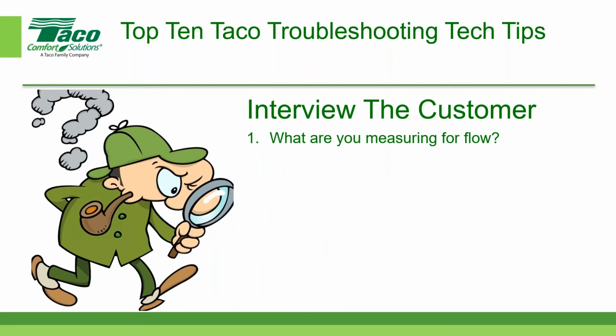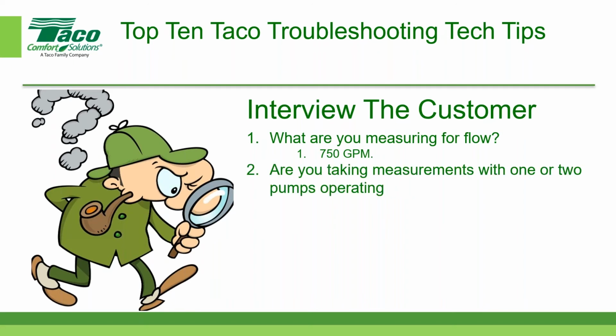So then I said, well, what are you measuring for flow? Well, the design condition we just said was 1,000 gallons per minute, and they come back and tell me they're measuring 750 gallons per minute. Now, we still don't know exactly what the problem is, but we're starting to narrow things down a bit. So I said, are you taking measurements with 1 or 2 pumps operating? Now, this is an extremely important thing because if you have 2 pumps operating in parallel and you have the operating data for 1 pump, then you need to just run 1 pump. Now, you're not always allowed to do that because of existing operating conditions, but if at all possible, run 1 pump so we can determine the operating conditions of 1 pump as opposed to 2 pumps running in parallel, because it gets a little more complex when we're trying to troubleshoot 2 pumps running in parallel. So we have to establish the performance of 1 pump.